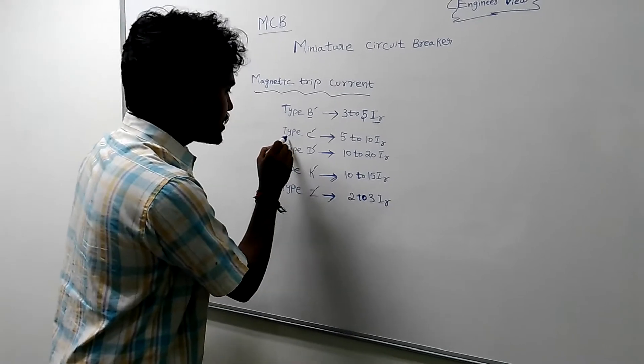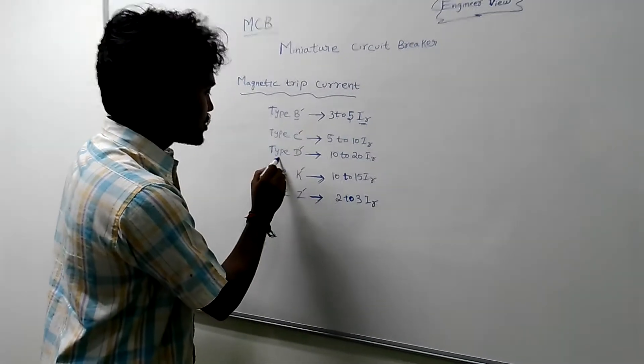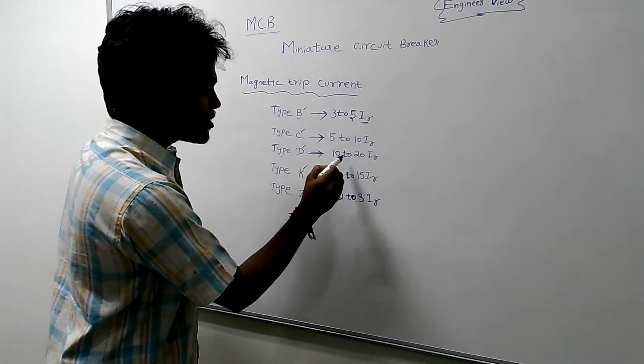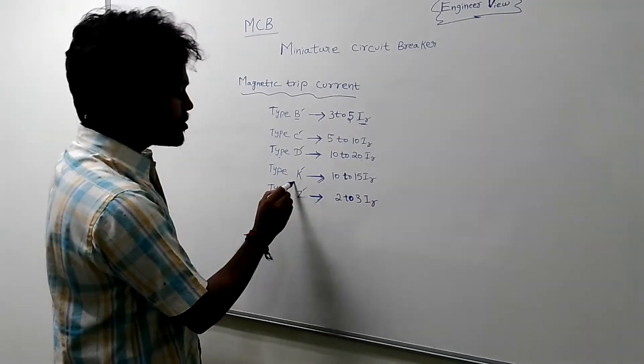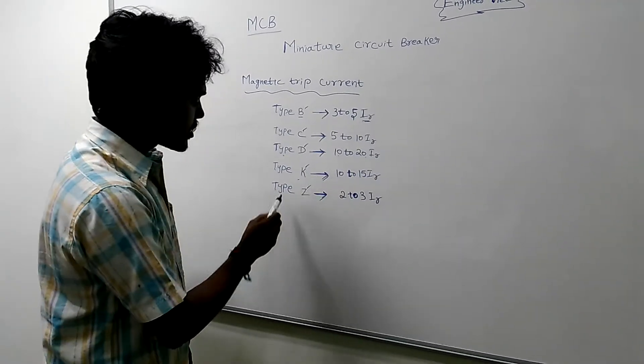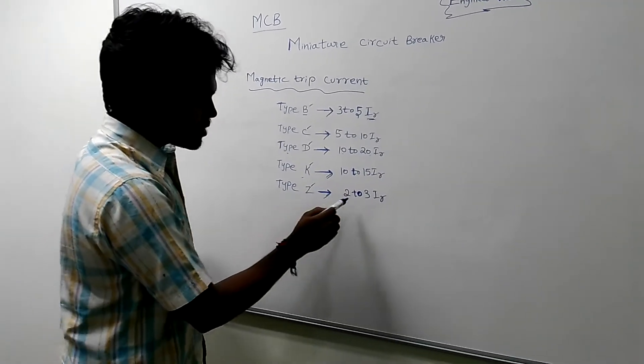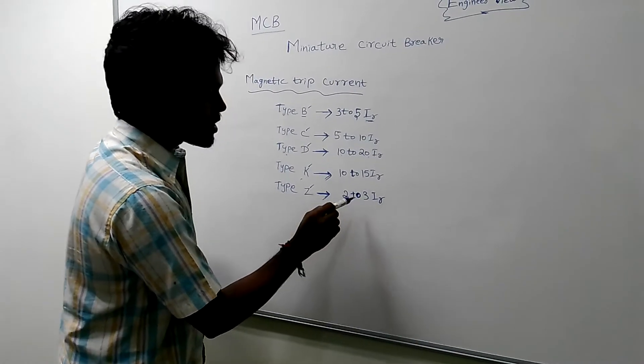Type C trips at 5 to 10 times the full load current. Type D trips at 10 to 20 times the full load current. Type K trips at 10 to 15 times the full load current. Type Z trips at 2 to 3 times the full load current.